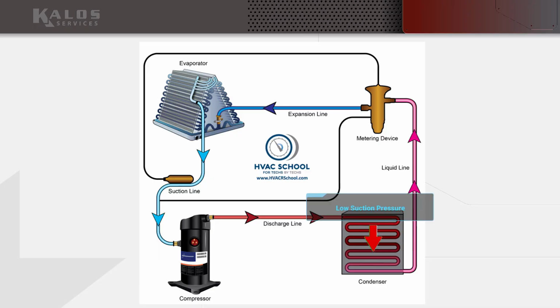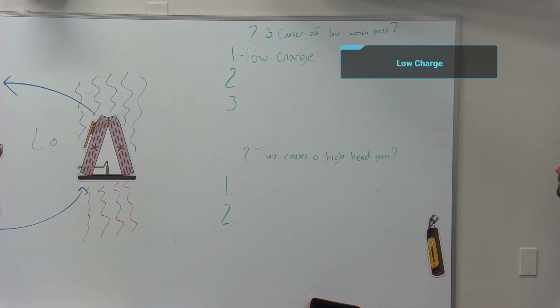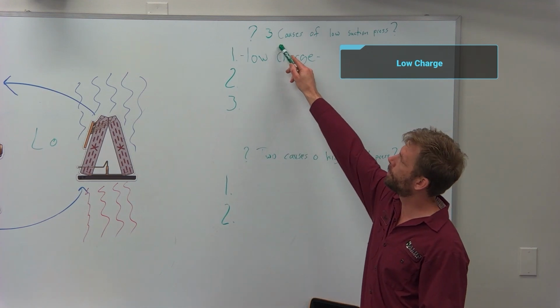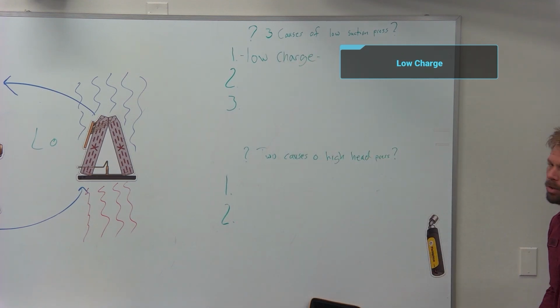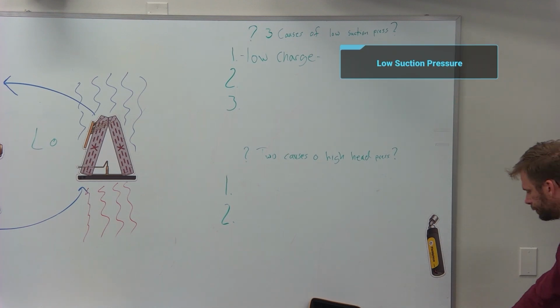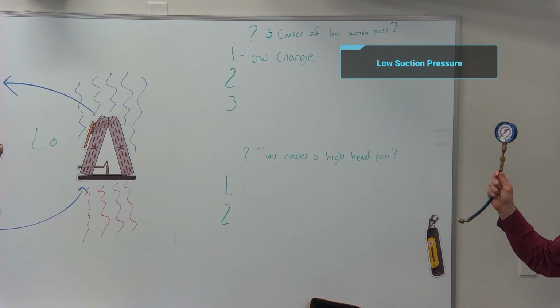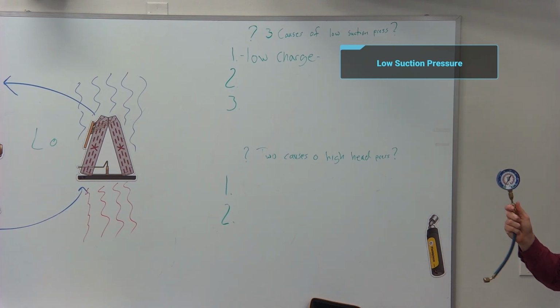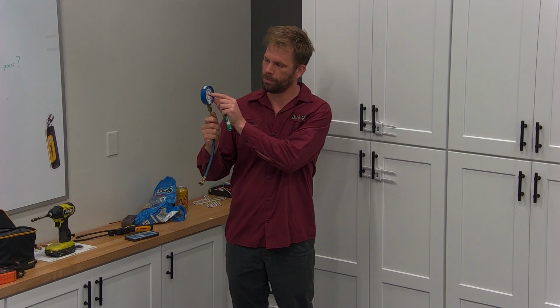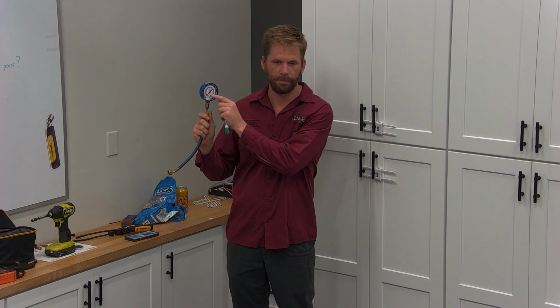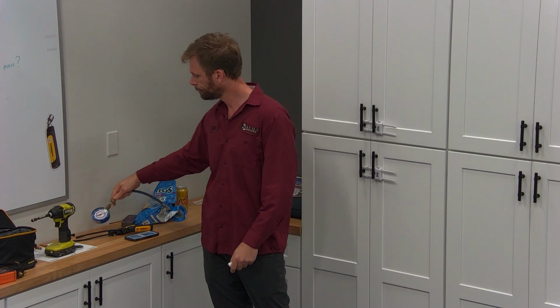Here we go, common causes. Low charge is one of the three most common. I didn't write down the words most common, but I want the three most common. So low charge is one of the three things that can create low suction pressure. What is low suction pressure? It's the low pressure read from our suction line. Low suction pressure means low saturation as well. Could be freezing, could be that low.